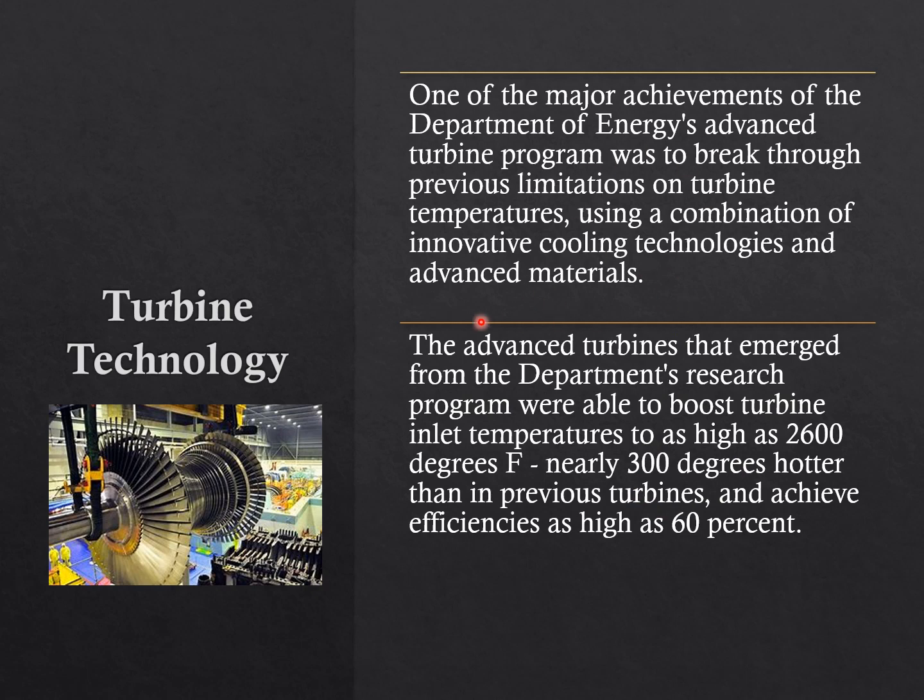By working on these issues, researching, and developing better technologies, the Department of Energy research program can boost the system temperature, which is your turbine inlet temperature, and we can now go all the way to 2600 degrees Fahrenheit, that's 300 degrees Fahrenheit up from the normal 2300 system. That's pretty good. If you calculate the efficiency, that's about 60% efficiency.